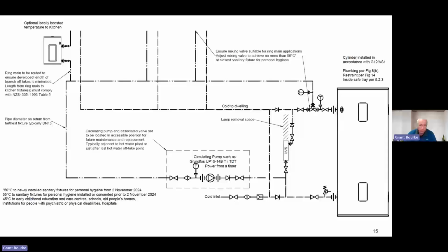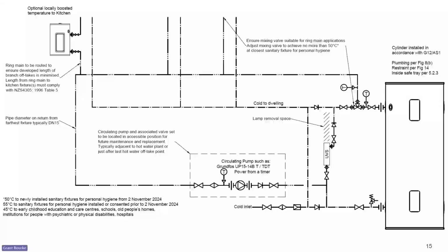If we look now at a warm water ring main, which is similar but different. So we start out with the mixing valve. So what this is, it's kind of like a domestic tempering valve, but not quite. It's going to mix hot with cold and keep the whole ring main down to a lower temperature. Now, it's important that you talk to your supplier and read their specifications to make sure that the mixing valve you've chosen is going to work in this application.